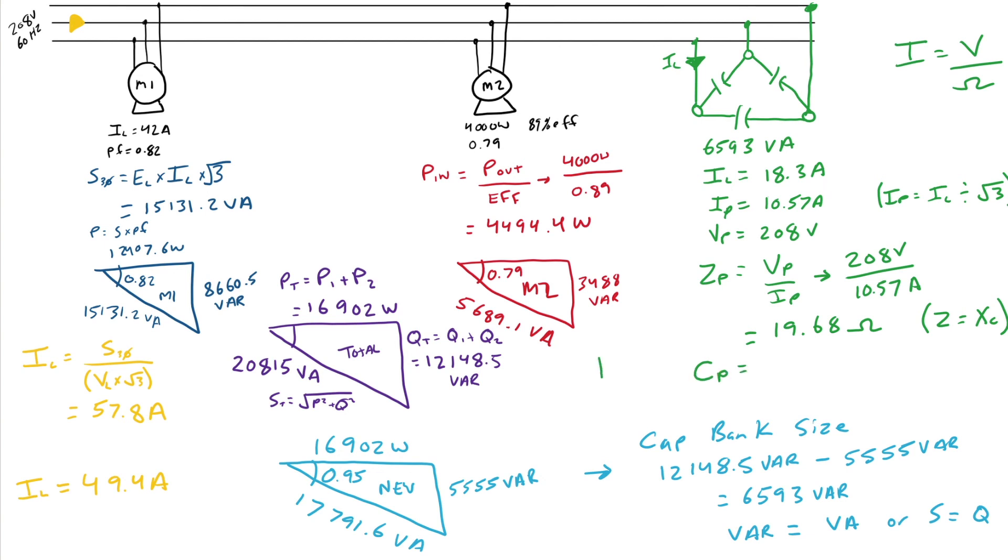So, the very last step that I want to do here is I want to figure out the capacitance of each capacitor. So, I'm going to take my formula of 1 over 2 pi Fc, and I'm going to transpose it to be 1 over 2 times pi times frequency times reactance. And in this case, I find out that each capacitor needs to be 135 microfarads. If they're connected in delta.